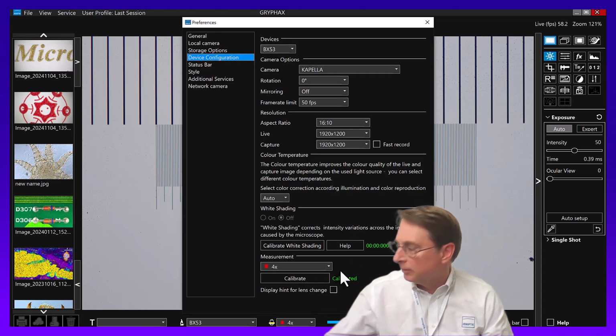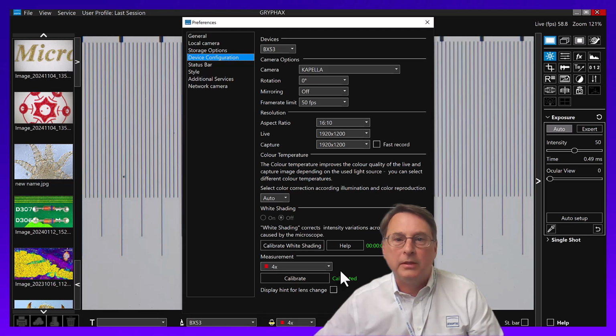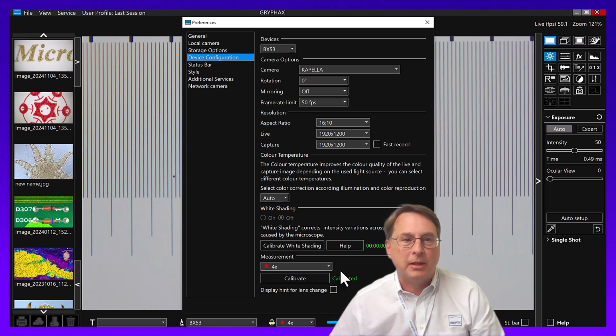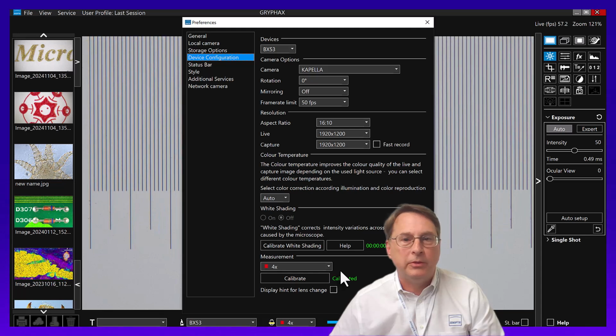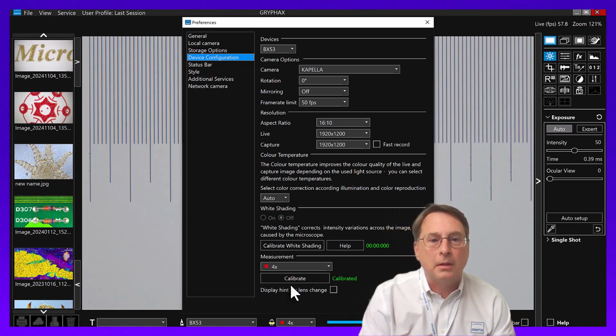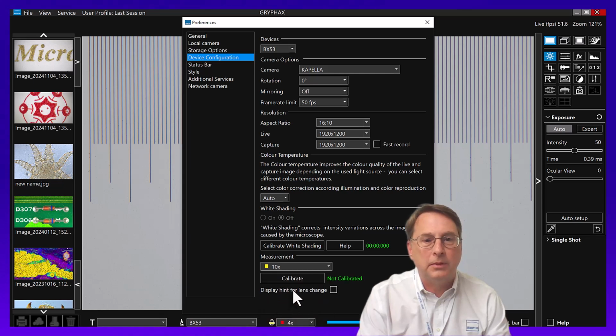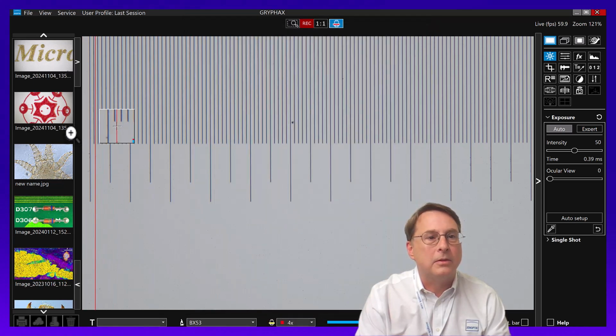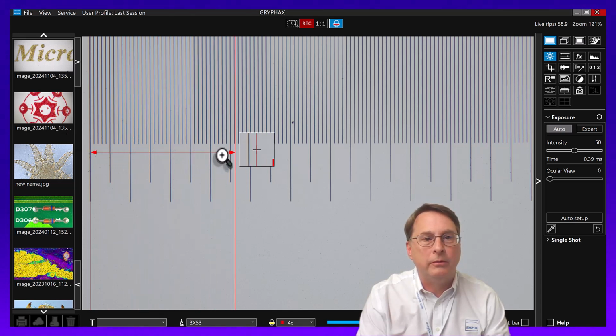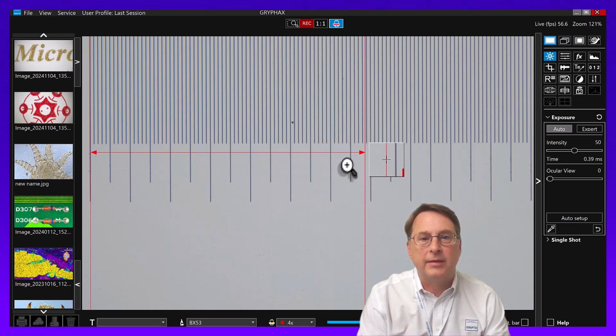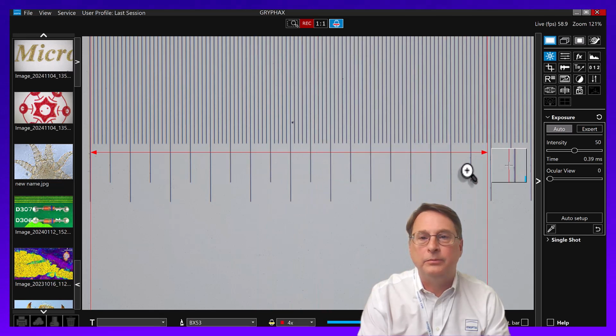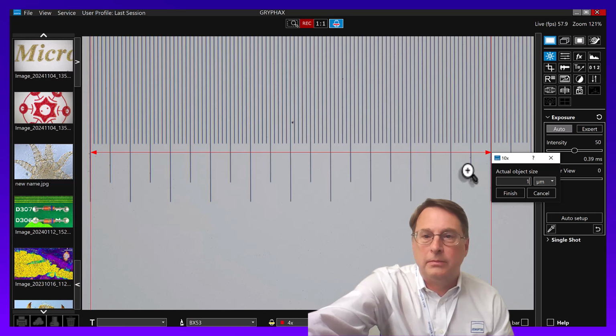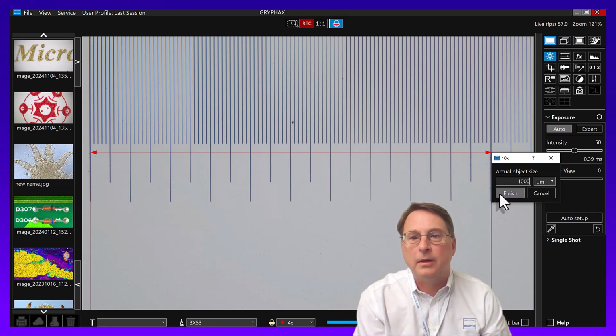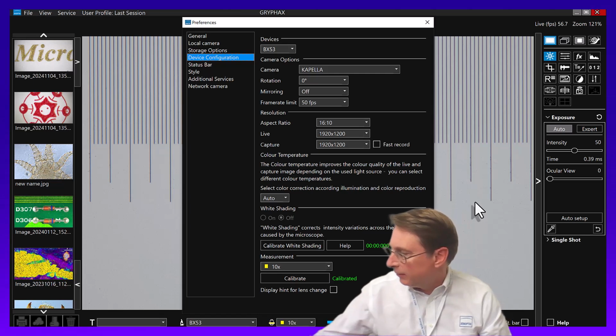Then I'm going to do my next objective. So that's going to be a 10x. Focus that in. This time I can't get the whole 2 millimeters in. I'm going to choose 10x here. Calibrate. So once again, 100, 200, 300, 4, 5, 6, 7, 8, 9, 10. So there's 1,000 microns right there, 1 millimeter. So I will type in 1,000 and finish. So you're just going to do this for each objective that you have on your microscope.